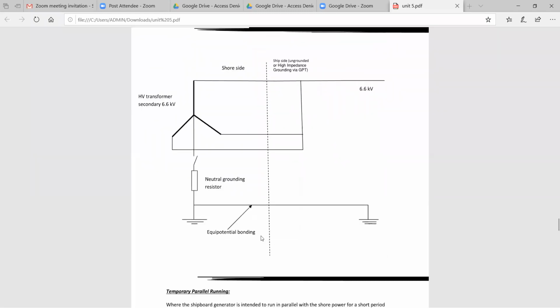And then the final one you have to consider is the neutral grounding resistor connected along with a switch. The high voltage transformer secondary side we have is 6.6 kilovolt. It can be connected to the ship side also. So on this side we have a neutral grounding resistor. The neutral grounding resistor is to be disconnected so that the system can be operated under the unbalanced condition.